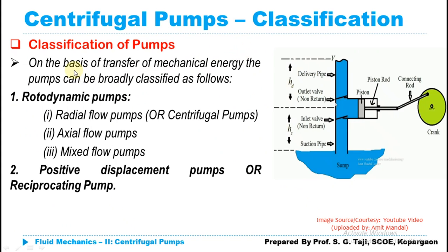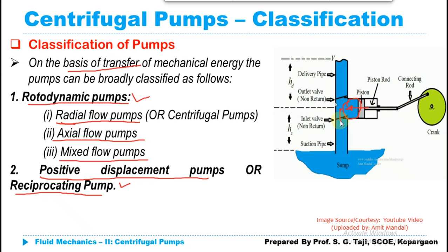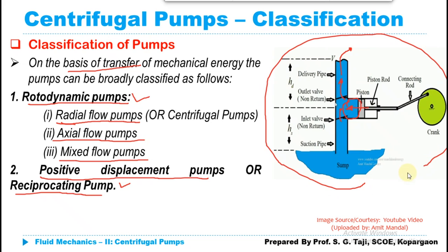On the basis of transfer of mechanical energy, pumps can be broadly classified as rotodynamic pumps and positive displacement or reciprocating pumps. The centrifugal pump is a type of rotodynamic pump, also called a radial flow pump. Other rotodynamic types include axial flow and mixed flow pumps. In a reciprocating pump, a piston rod operates non-return valves — when suction develops the inlet valve opens, and when the piston moves forward the outlet valve opens pushing water upward. A hand pump is the best example of a reciprocating pump.